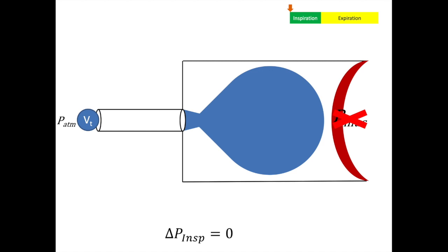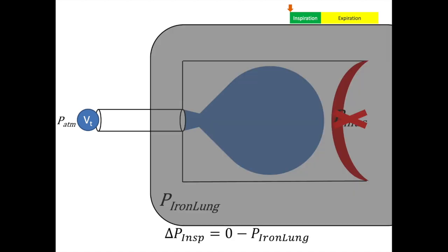This was the situation during the polio epidemic in the early and mid 20th century. Kids would get polio and their diaphragm would become paralyzed so that they couldn't create any inspiratory muscle pressure and they couldn't breathe in. Now the diaphragm works by creating a pressure that is less than atmospheric pressure, and that's a negative pressure. So we breathe in by creating a negative pressure. They took that same concept and created the iron lung. And the iron lung was a big tube, essentially, that the patient lay in with their head outside the tube so that their mouth would be open and exposed to atmospheric pressure.